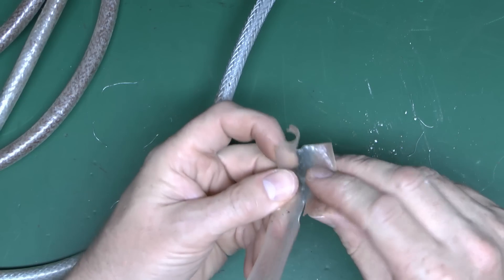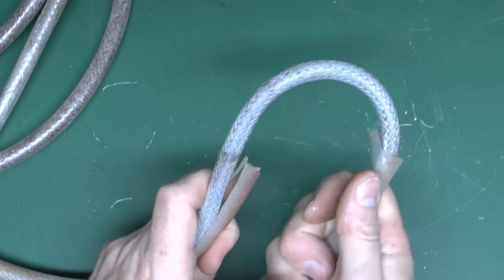This isn't actually as bad as some of them can be, but you can see it's certainly not a particularly robust cable. So that's SY cable. A cable which is not an armoured cable, it is not suitable for use outside, it is not suitable for use for burying in the ground, and quite frankly it's not suitable for use in a whole pile of places that some people seem obsessed on using it in. It can be used in particular places, such as a cable going to a piece of machinery if you need a screened cable for that, but certainly in terms of thinking it's an armoured thing and it's OK for outside, because it rusts, deteriorates, the outer sheath is damaged by sunlight, and it basically disintegrates.